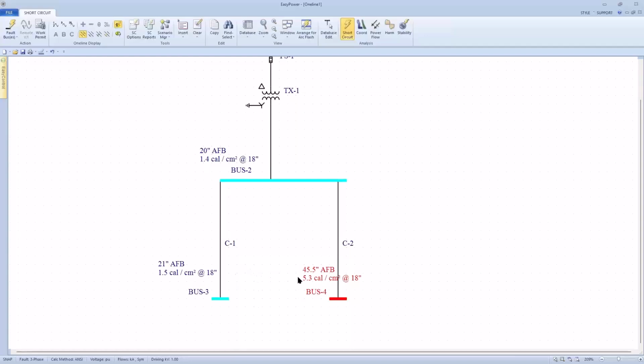But if I walk 1,000 feet away, now my arc flash boundary has doubled, my incident energy has tripled, and you're telling me I need to put on more PPE to work on this bus hot. How can that be? I said, yeah, what are you talking about? He says, Jim, I've been an electrician for 25 years, and anybody that works with electricity knows the farther away you get from your energy source, the lower the energy is going to be. Your tool's telling me this energy goes up. How can that be? My response was, I've been an electrical engineer for 25 years, and I agree with you. I don't see how that energy can be increasing.